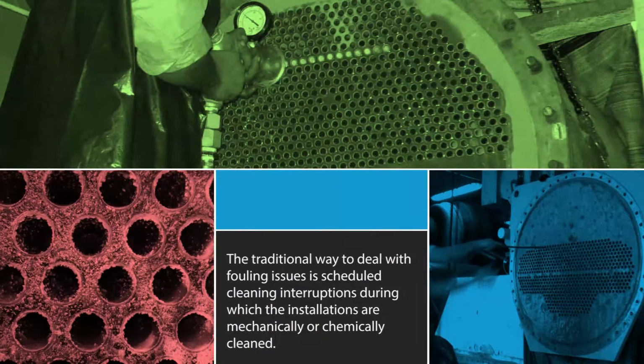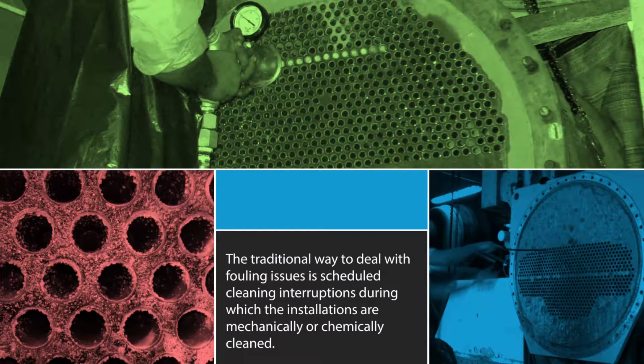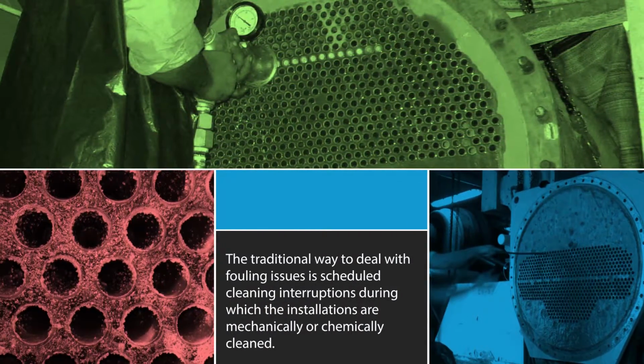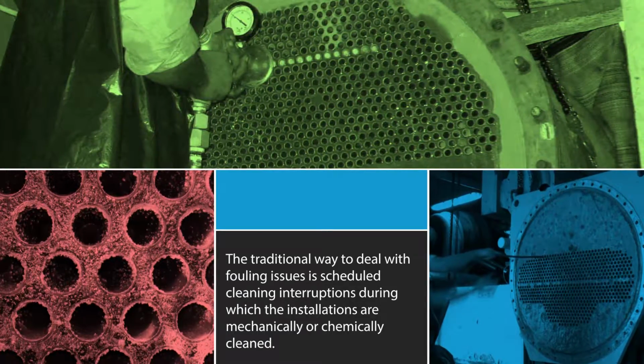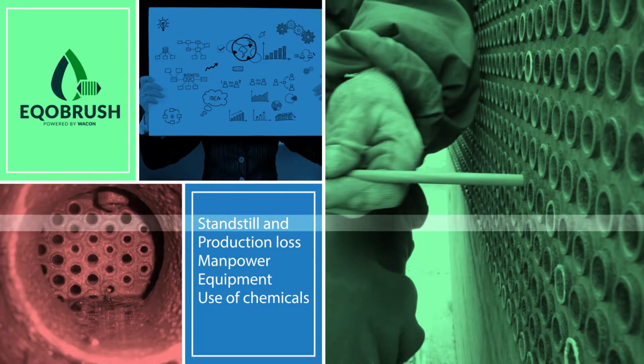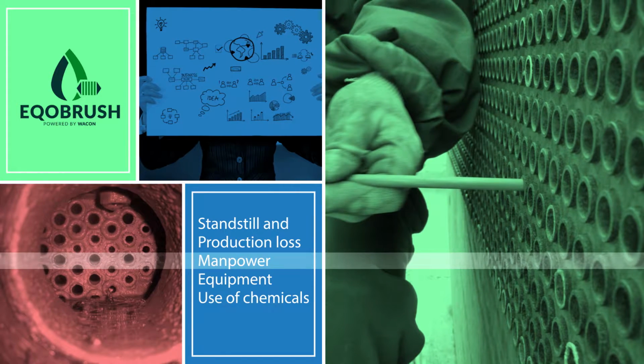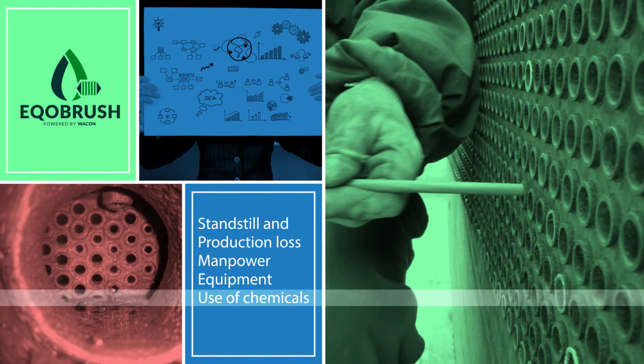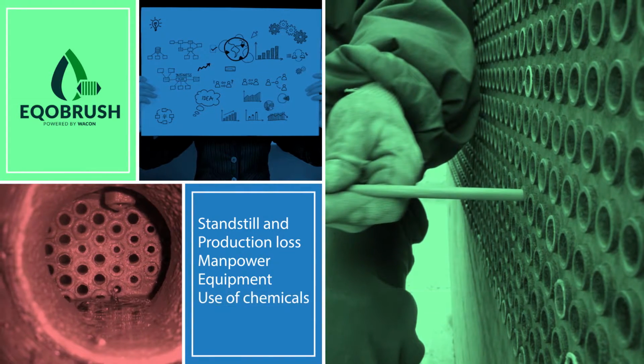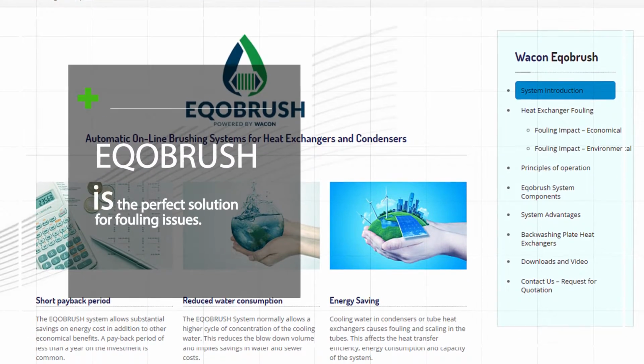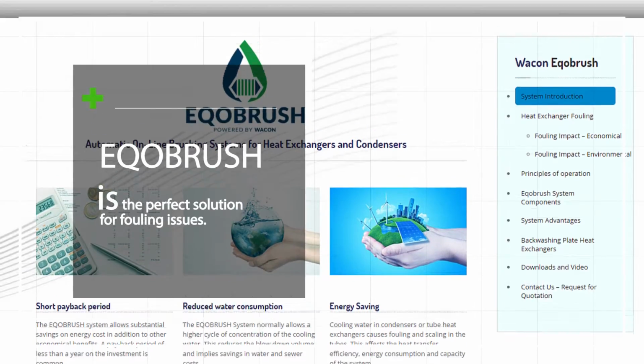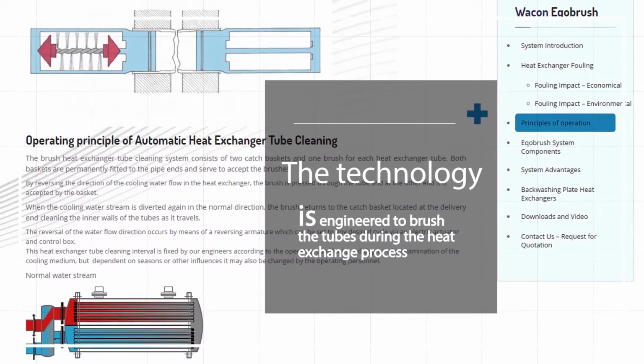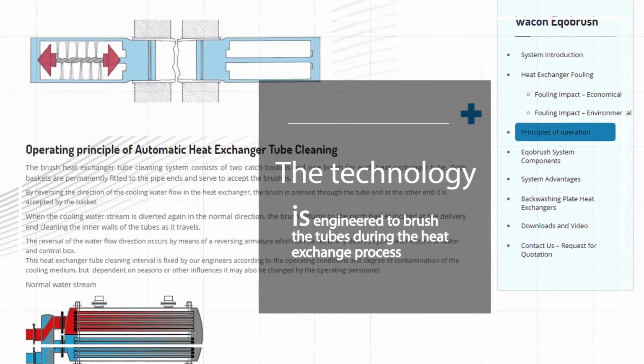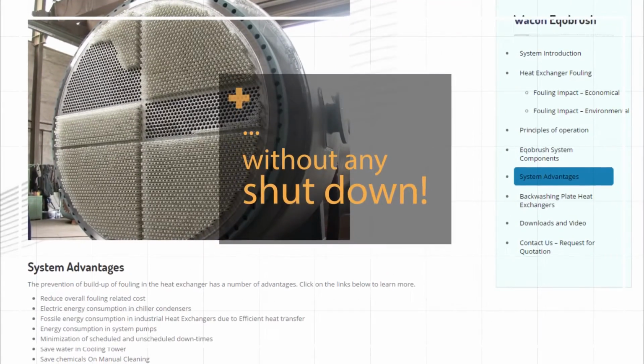The traditional way to deal with fouling issues is scheduled cleaning interruptions, during which the installations are mechanically or chemically cleaned. Standstill and production loss, manpower, equipment, and use of chemicals are factors that add up to the total fouling-related cost. Eqo-brush is the perfect solution for fouling issues. The technology is engineered to brush the tubes during the heat exchange process, so without any shutdown.